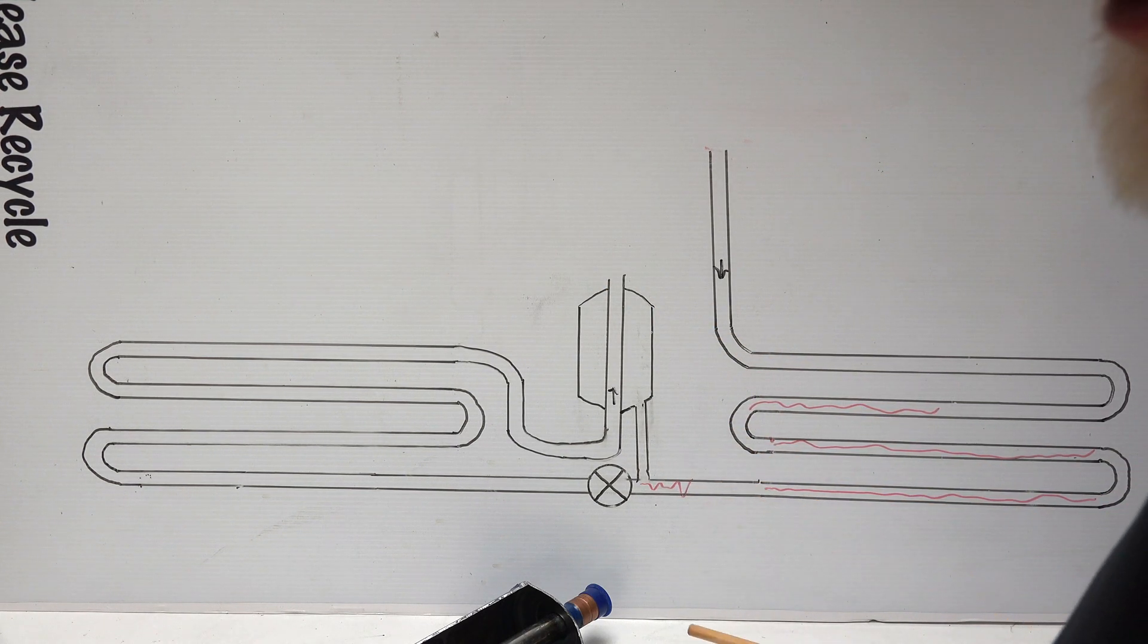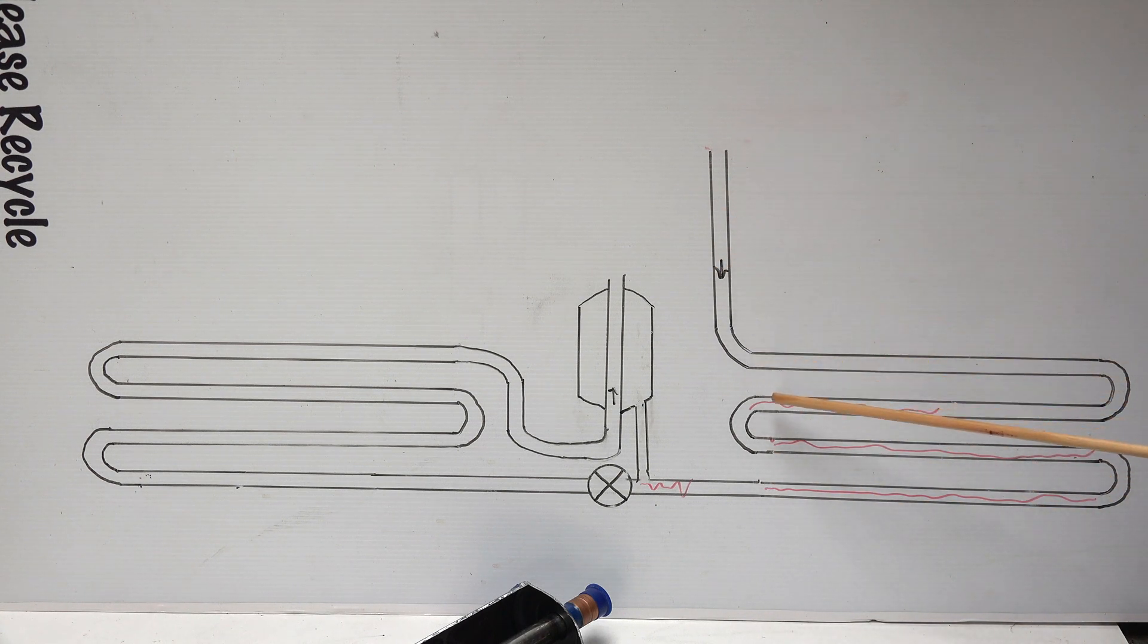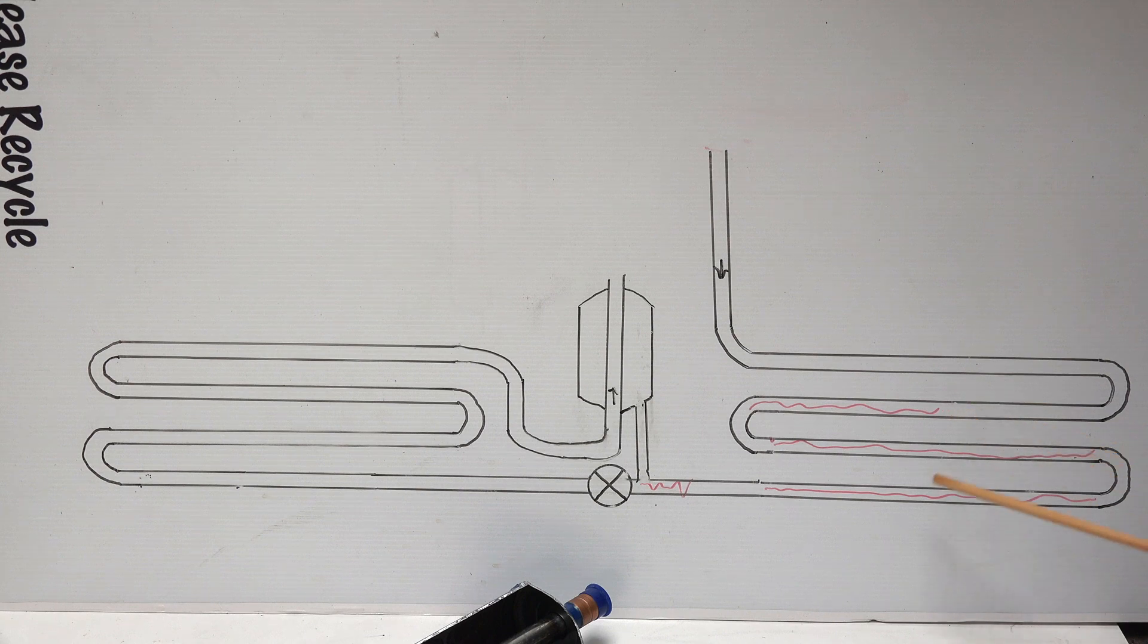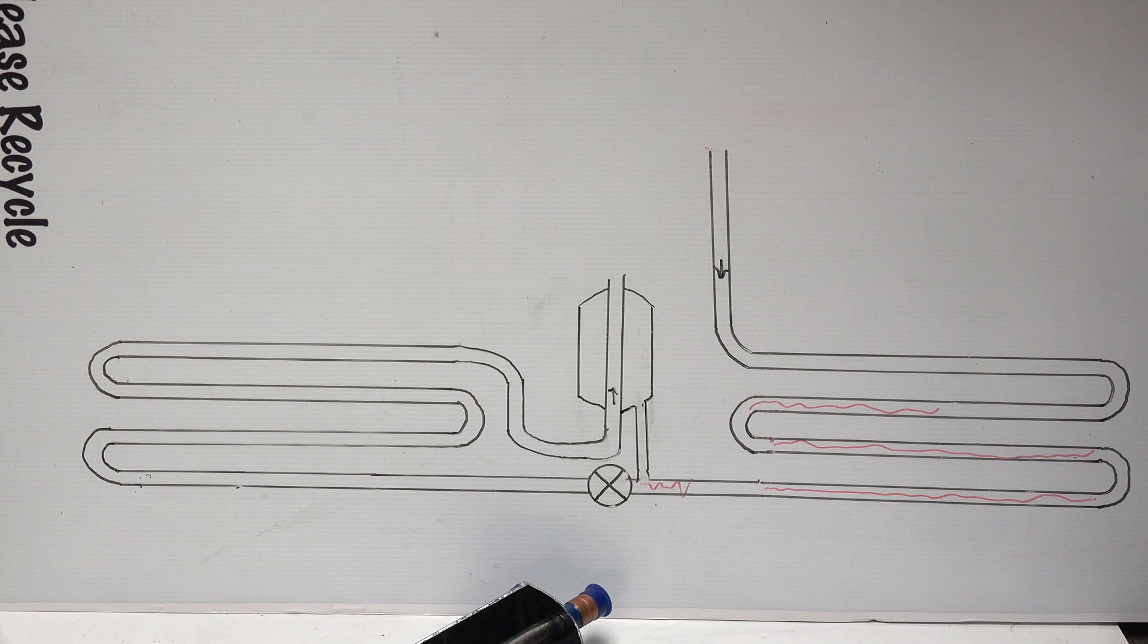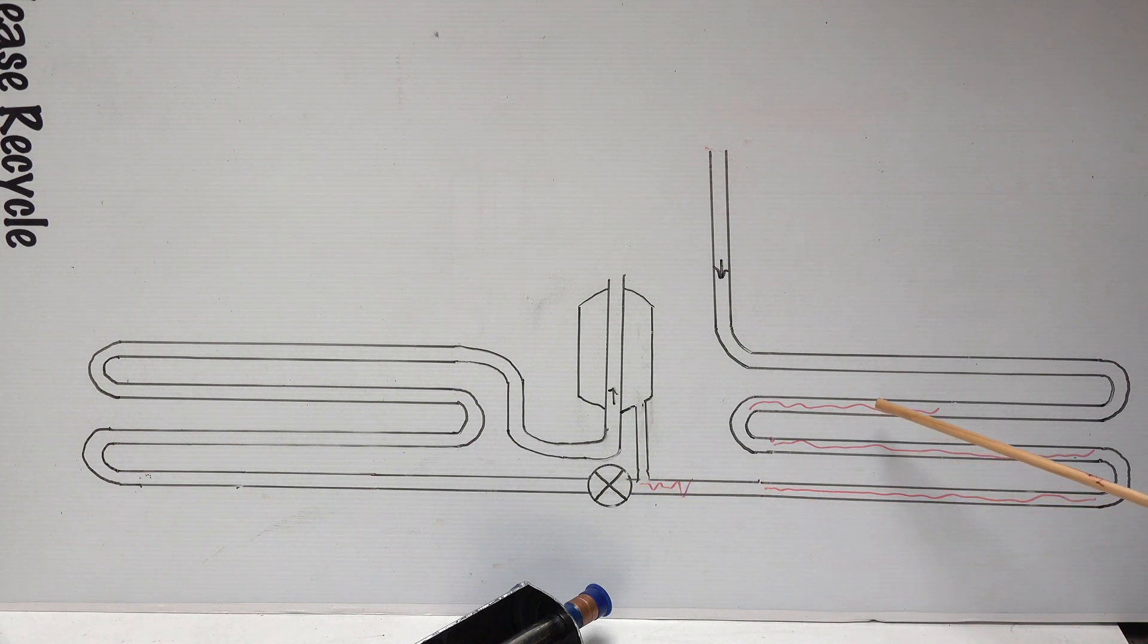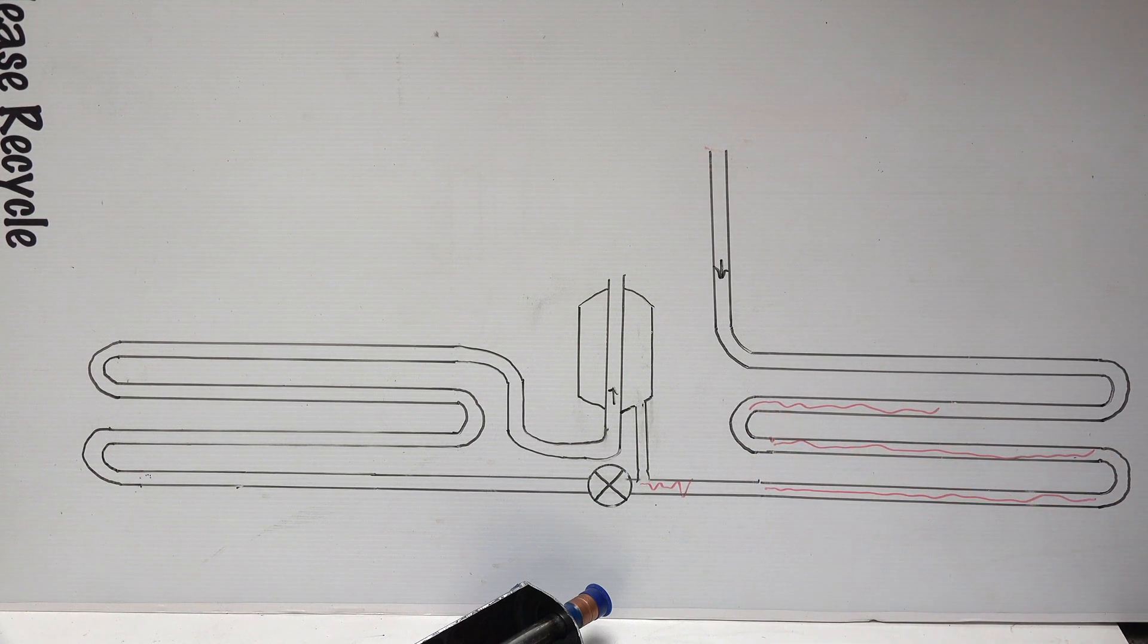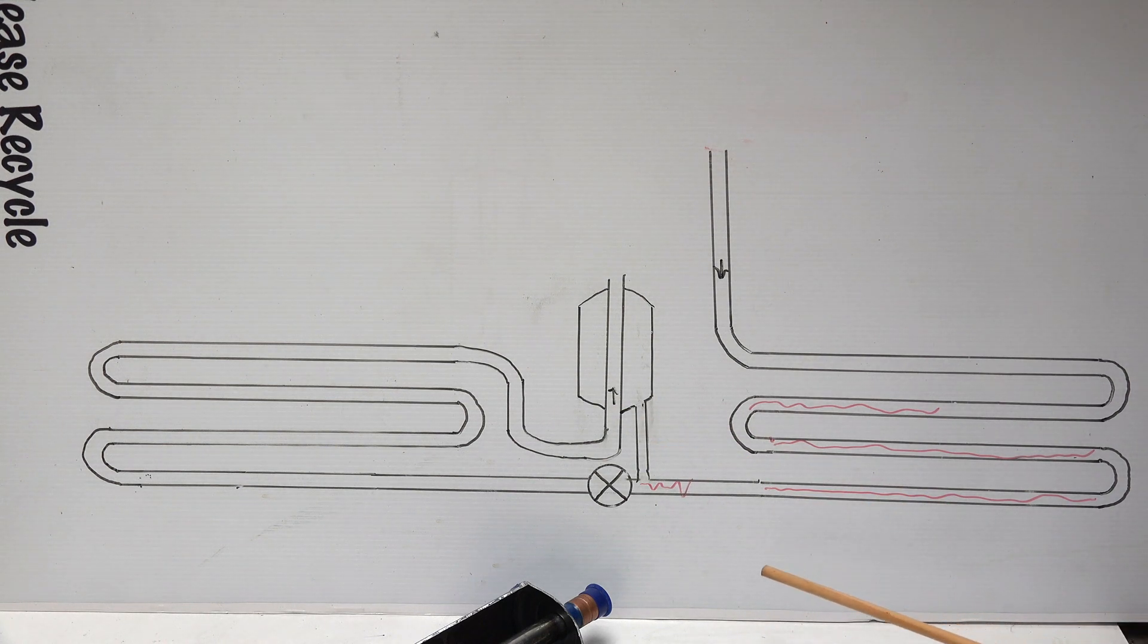So as the refrigerant starts to build up here and fills up these coils, then it is going to feed into this thing. Why does it go in there? It goes in there because it's cold and refrigerant likes the coldest place. So it's going to start drawing refrigerant out of that condenser and tend to balance it closer.